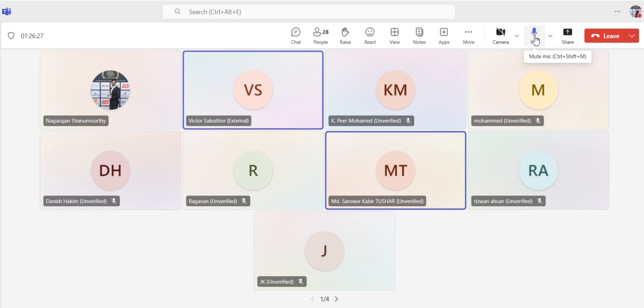The bypass line is only for this example; there is a system. Constant and variable pumps are there, right? You need to know the difference between constant and variable pumps. So why are you using secondary variable and primary constant, or why are you using both variable? You need to know this difference, then only will you understand why I'm considering the entire loop or only a partial loop.